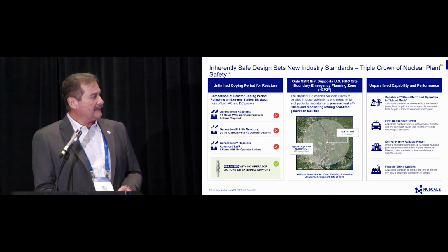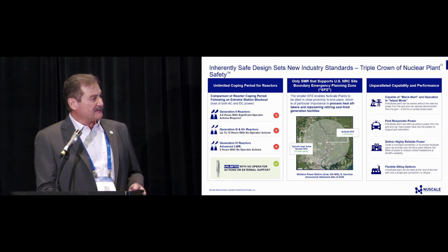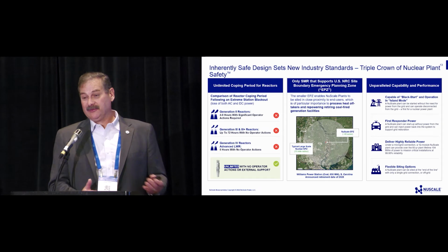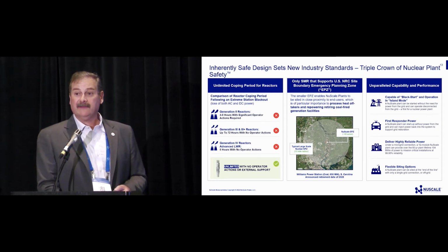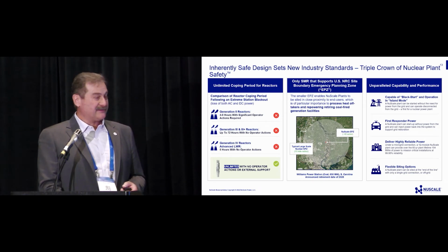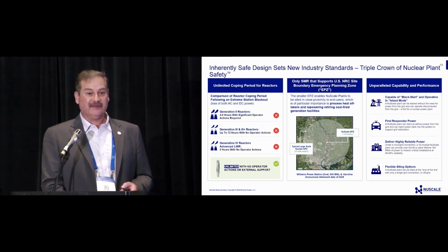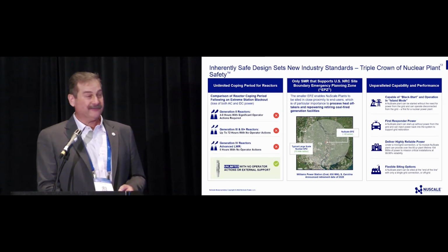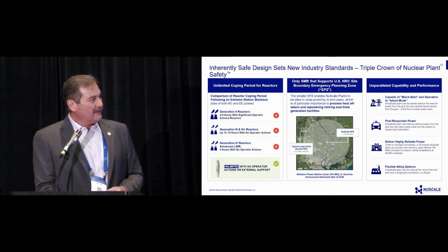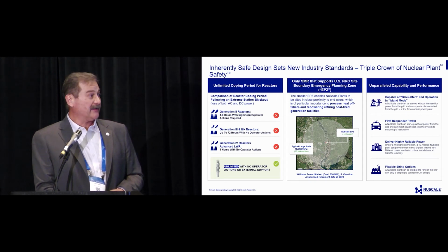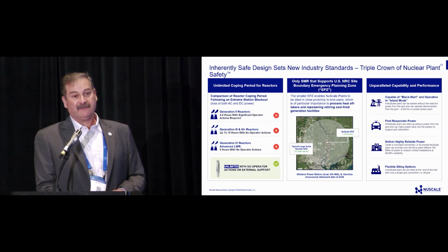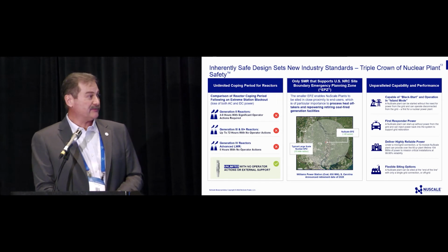Small emergency planning zone. You can see on the map, like a typical large scale, the zone that you have to show protection for. It makes it even more suitable to put in a place where there was an existing plant because you don't have to rezone the area for that and unnecessarily aggravate a lot of the public perception of what living next to a nuclear plant is like. We're capable of what they call black start capability. We don't require any offsite power to start up a unit. We have first responder power, so after a total system grid loss, we could be one of the first responders back.